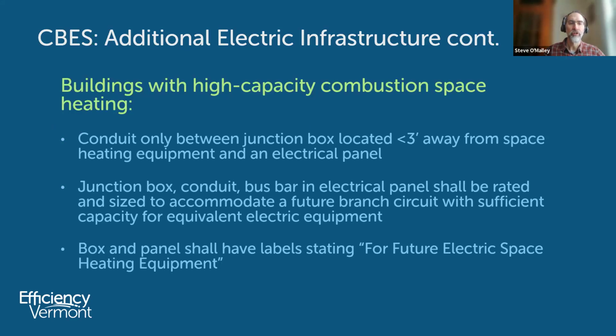The junction box, conduit, bus bar, and electric panel shall be rated and sized to accommodate a future branch circuit with sufficient capacity for equivalent electric equipment. So electrical engineers will have to think about what the design would look like if the building were heated and cooled with air source or ground source heat pump equipment, and build that into the branch circuit and electric panel that's installed.